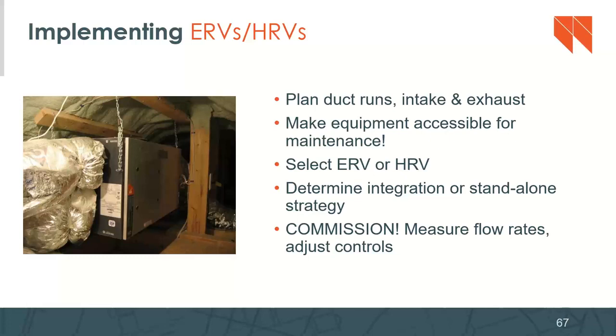I've seen 6 months up to a year, but in practice, there's a lot of air usually being moved through these pieces of equipment, and it's happening 24/7. Outdoor air can be dirty. There's a lot of stuff in it. Not only do the filters of the machine itself need to be changed, but you've also got to take a look at your outside air intake ports. A lot of lint and stuff from the ambient air can get stuck as it's brought in through the system, because usually we want a pretty wide mesh to keep any rodents or birds or anything from getting into that ventilation ductwork. But either way, there's some maintenance that needs to go on.